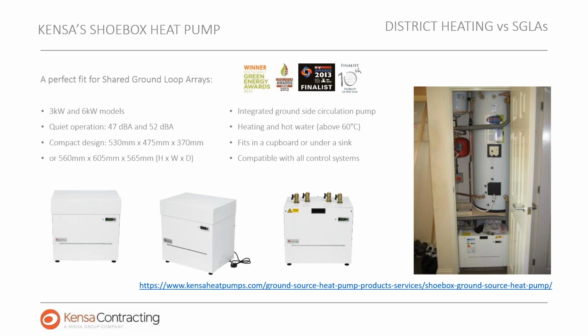As I say, it has an integrated ground side circulation pump, so the unit will pump the low temperature liquid coming from the ground itself. The heating and hot water, we can supply up to 60 to 65 degrees centigrade. It fits in a cupboard or under a sink, as I just explained, and it's compatible with all control systems. The typical controls that come with the Shoebox unit are Honeywell controls and a very basic thermostat. The system has been designed not only to utilize as much as possible the free energy within the ground, but also to be easily controlled and used by the owner of the property or the tenants. So try and keep it as simplistic as possible for usage.